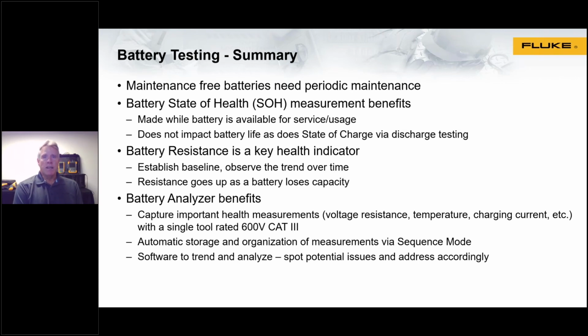Battery resistance is a key health indicator that can provide insight into one of the various different number of problems that could be occurring. So practice there, establish a baseline, either if you know or measure good batteries, or by getting the average value in strings, that can be useful to have something from which to compare. And then what's really key though is to observe the trend over time. Resistance goes up as a battery loses capacity, so that's what you're looking for.